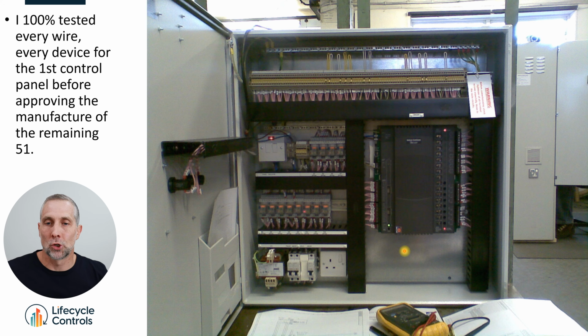So I went to the factory. I tested this control panel, every single wire. I tested every wire, every relay. I downloaded a little dummy program into here. I made sure this was perfect. I spent like 4 hours testing this panel. Then I gave the panel manufacturer approval to build another 51 of those.